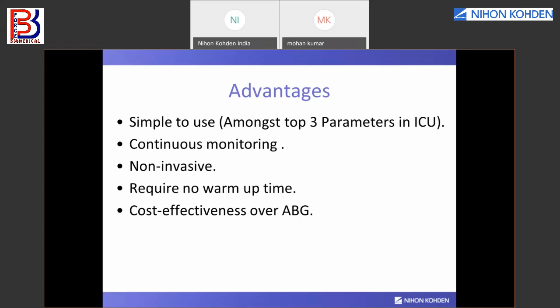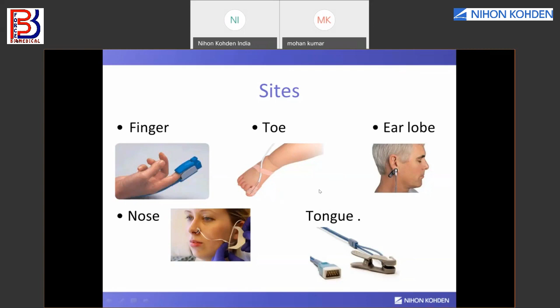So the sites where we can monitor SpO2: the basic method is attaching it on a finger. And in case of neonatal or infant babies, you can attach it on a foot. And in some cases where the perfusion levels are very, very low, where you cannot measure the SpO2 value on the hand or a foot, doctors normally go with the ear probe. There are also cases where doctors want to monitor SpO2 on the nose. And we also have a different kind of SpO2 probe which goes on your tongue, where you can monitor the oxygen saturation.